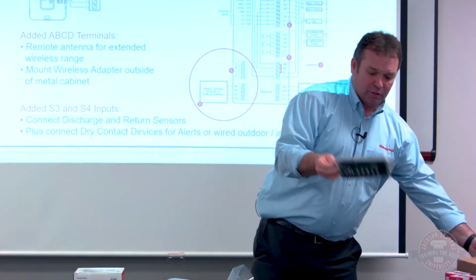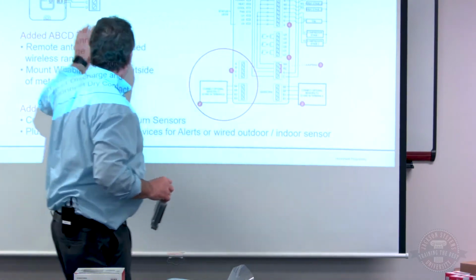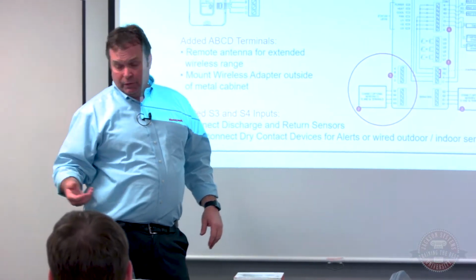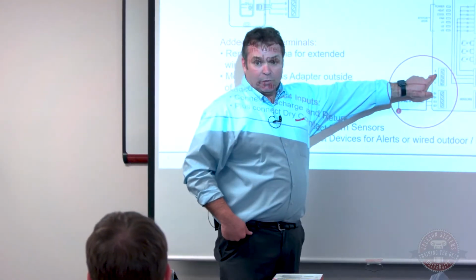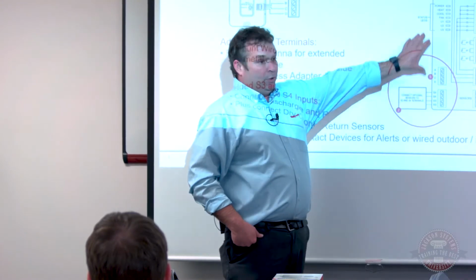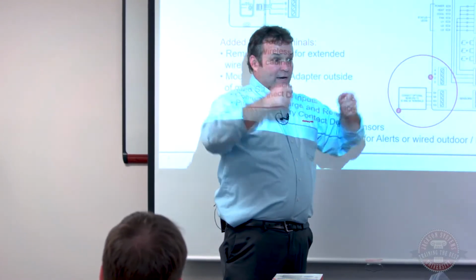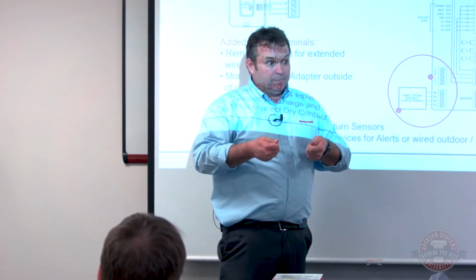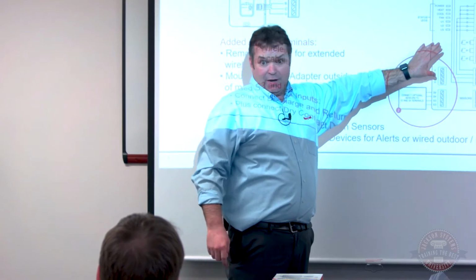So if I've got this above a roof line, I can take this wireless adapter module, which is the same one we use for zoning—there's an ABCD terminal here, and that's an antenna. I'd drop that below the roof line. I could mount it up in my equipment so I can get in through the roof hatch and actually work on it. Just make sure you don't put that up in a cabinet without dropping the antenna out of it, otherwise you'll have an issue.